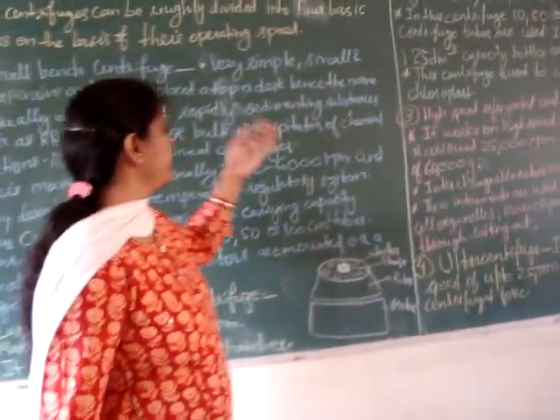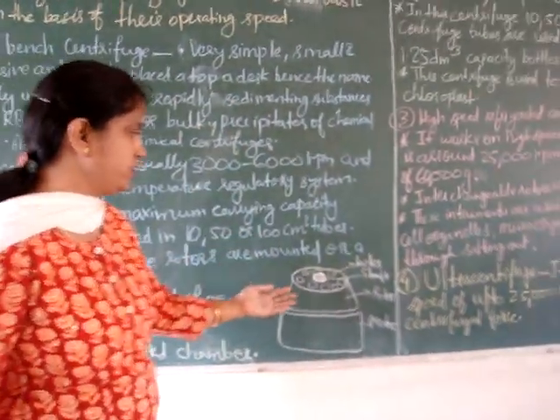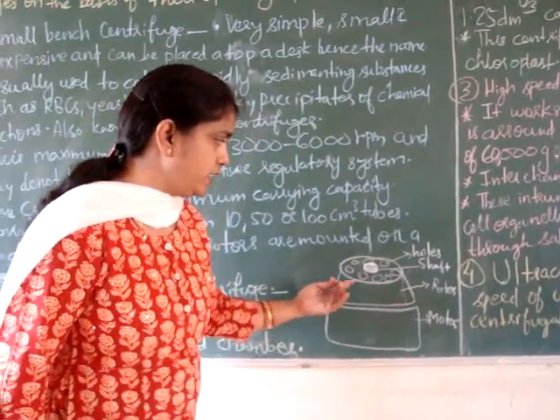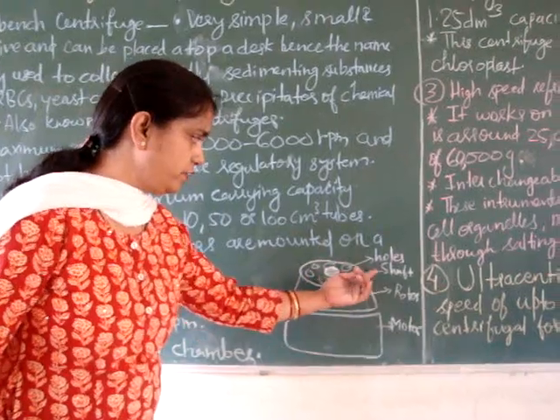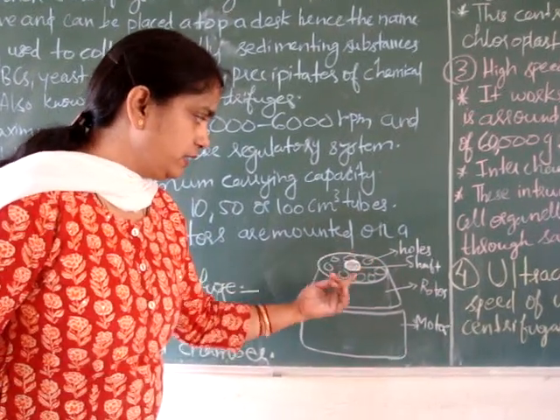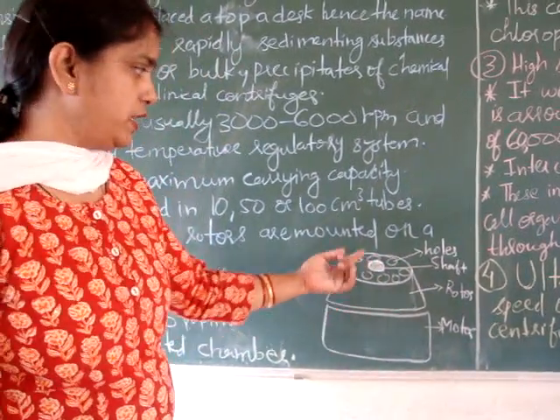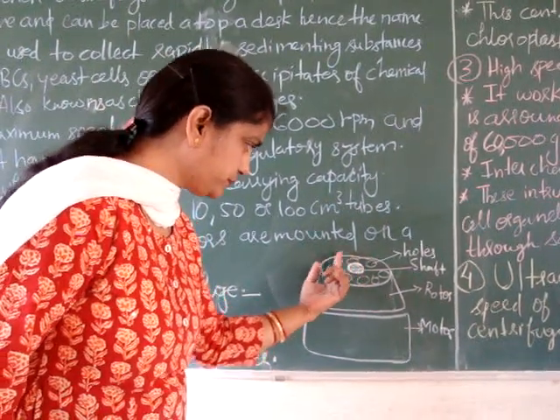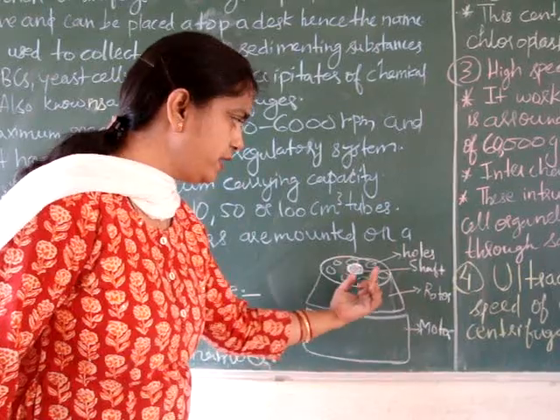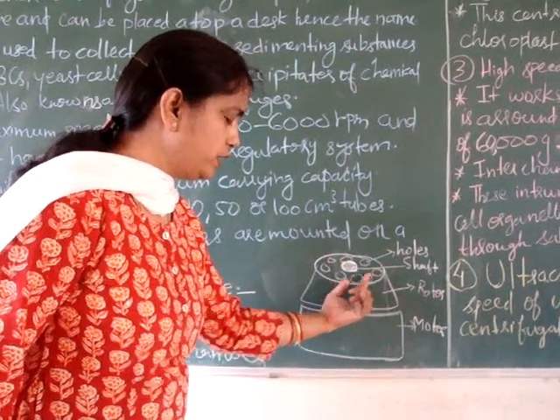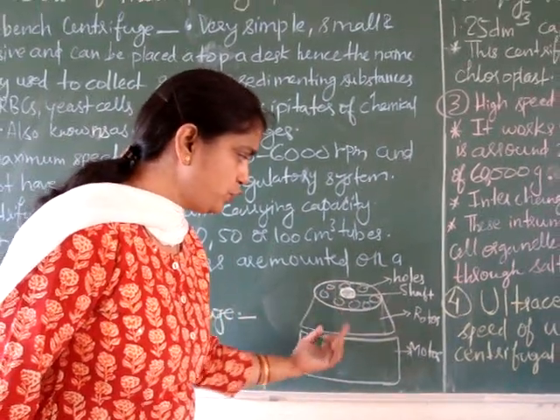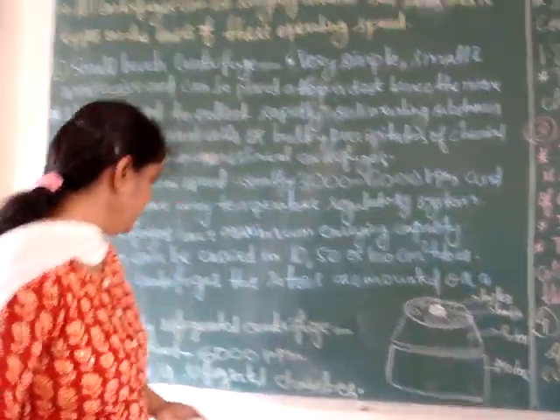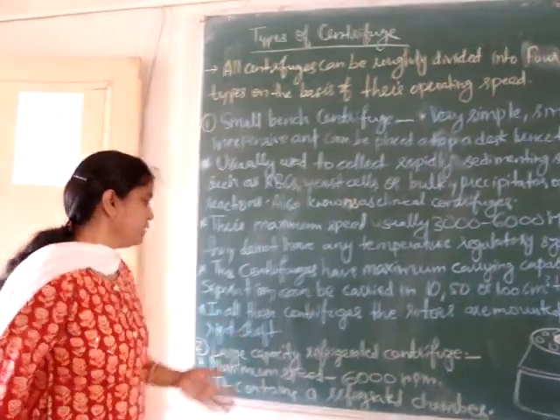In all these centrifuges, the rotors are mounted on a rigid shaft. This is a simple diagram of a desktop centrifuge — this is the rotor, this is the shaft, and to this shaft the rotor is attached. There are holes here for the centrifuge tubes, and this is the motor.